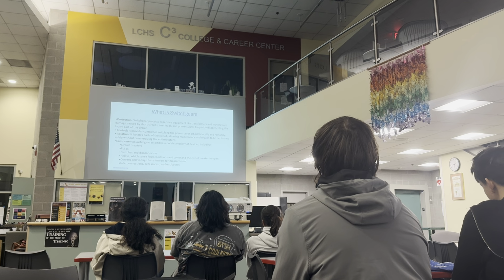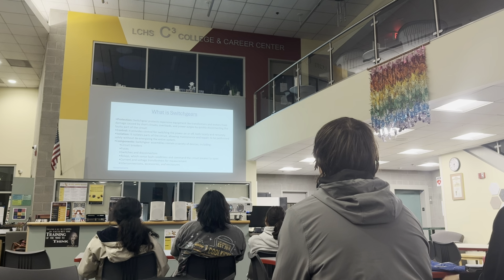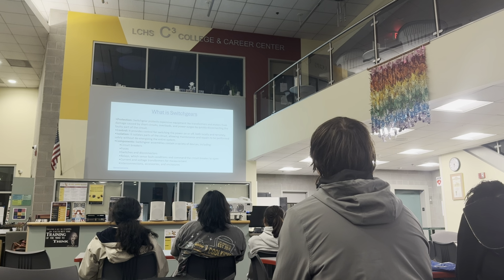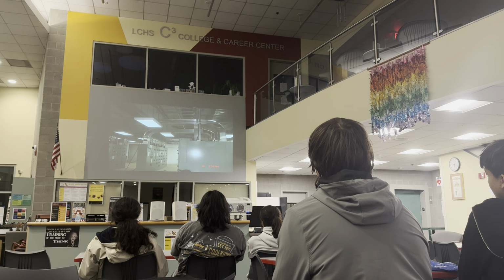Switchgear protects expensive equipment like motors. Motors are all expensive equipment. Extremely expensive. Like 12,000, 15,000, 5,000, 4,000 horsepower motors that are not cheap. So you protect them by putting in relays, protection for under voltage, short circuit, ground fault. Put all those relays in that switchgear. Okay? And each compartment takes care of one motor. So you saw there are several compartments. So each compartment takes care of each motor or each load. So they are separate. So that's how you distribute the power. Okay, so that's switchgear, and this is that switchgear I just showed you, and the power switchgear 13.8 kV goes back to the transformer.